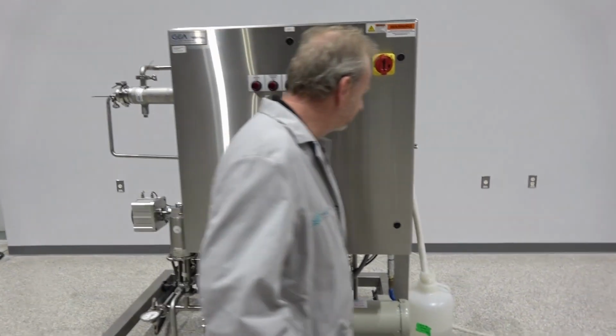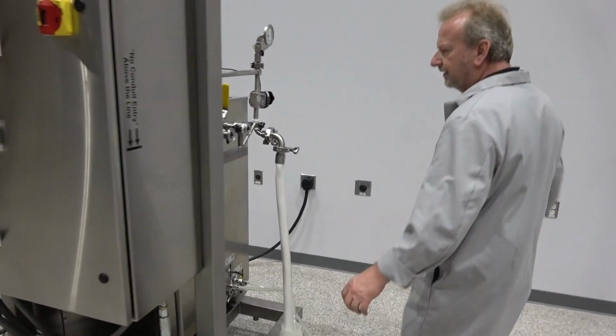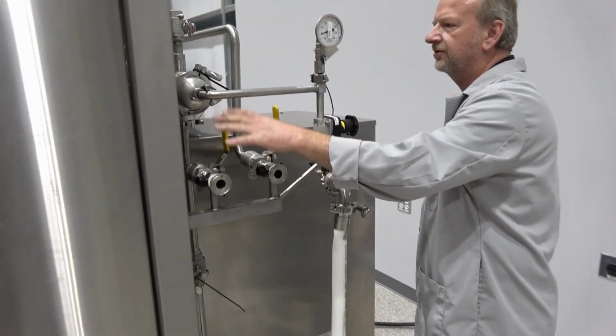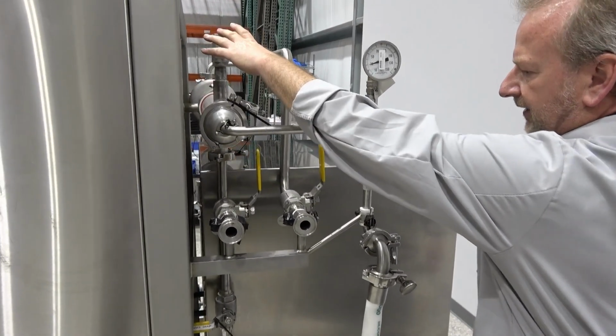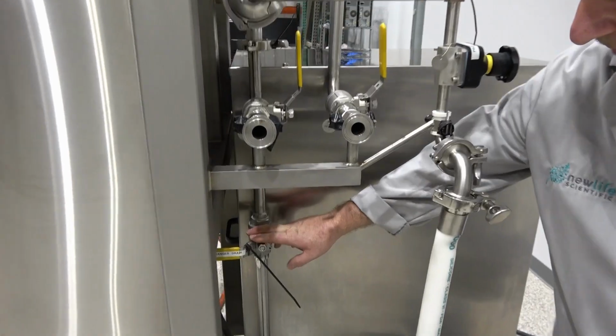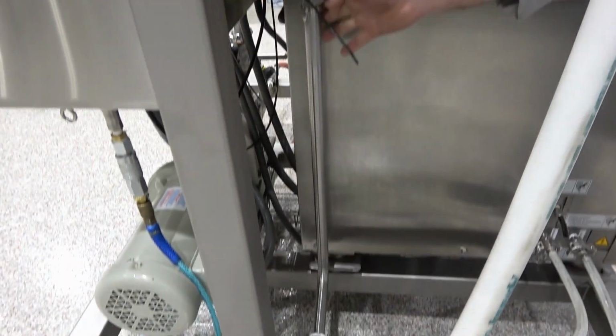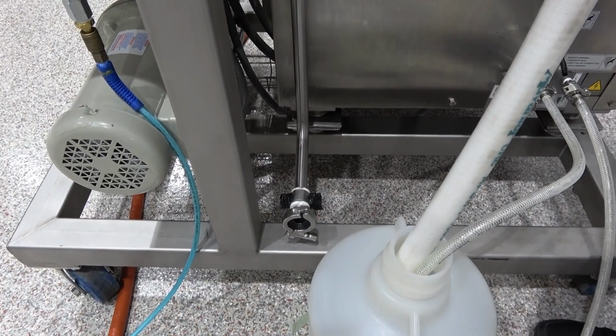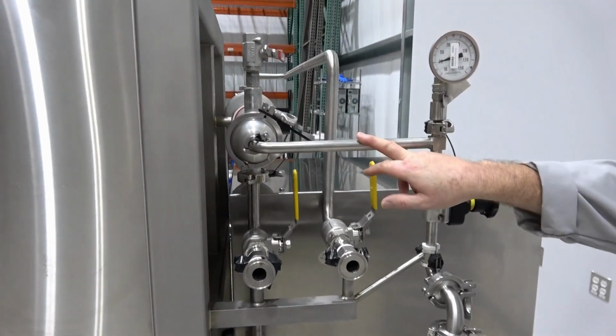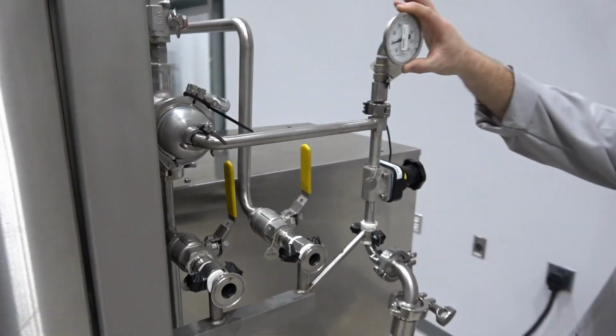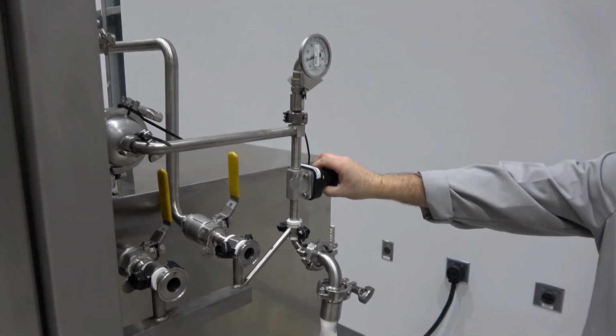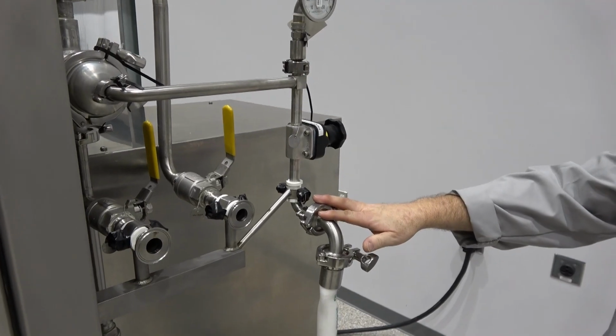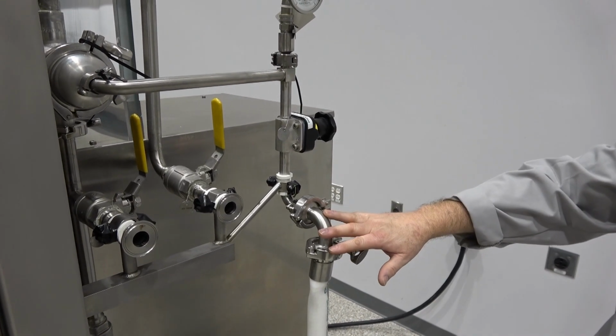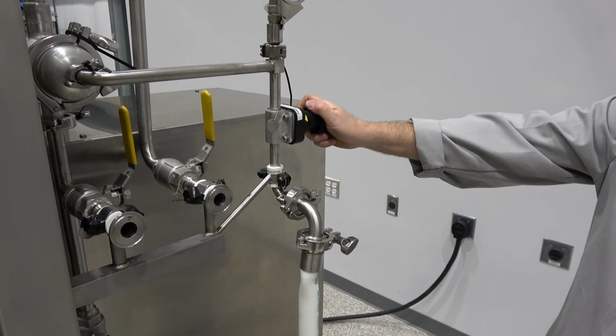We're coming over here now to kind of the other side. This is your chiller hookups here for your heat exchanger up on top here. It does have a vent here, and it also has a nice drain valve for your heat exchanger, and you can hook up there to get that drained out a little quicker. And then we also have the process fluid coming through, another gauge on this end to monitor, and then we also have a shut-off valve, so when we're getting ready to just unhook here, you can shut this valve off.